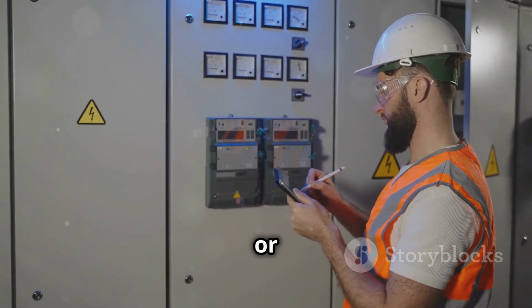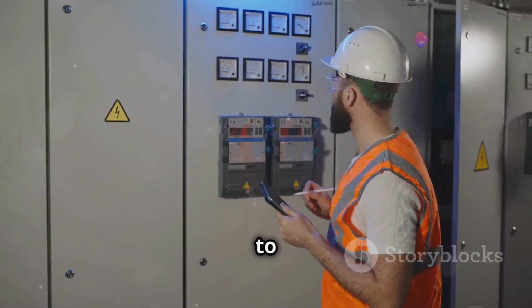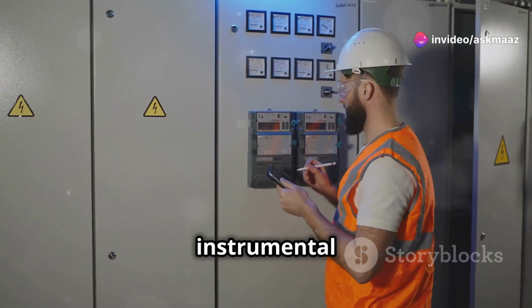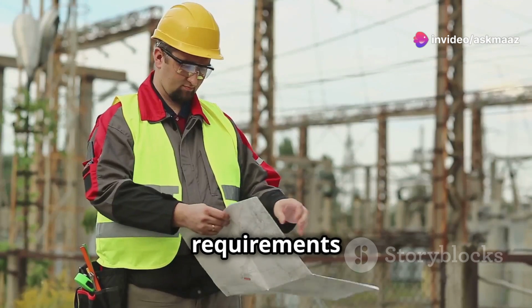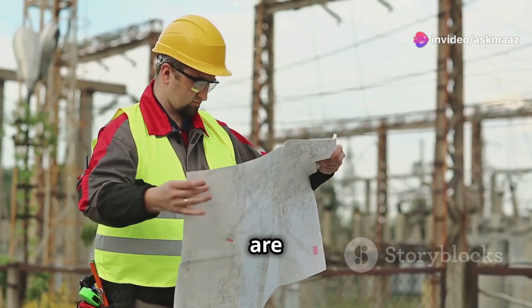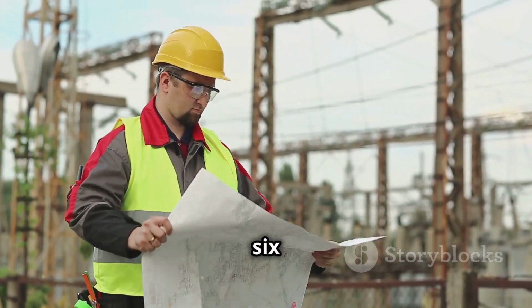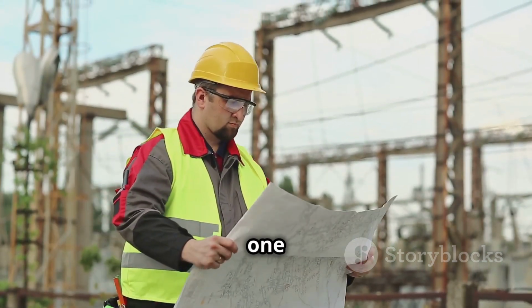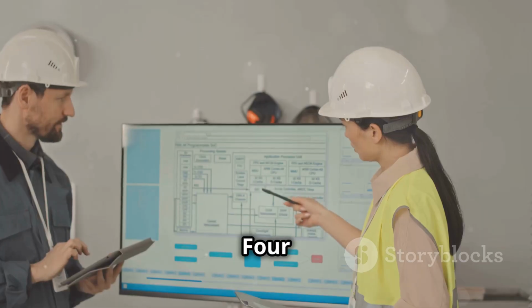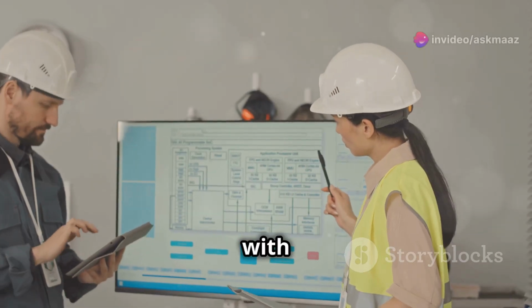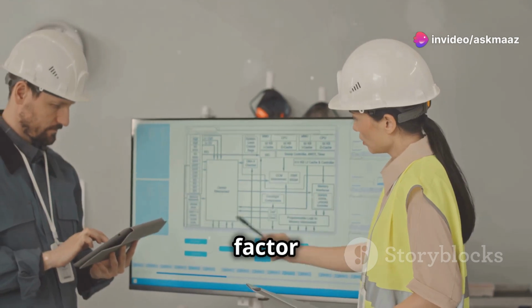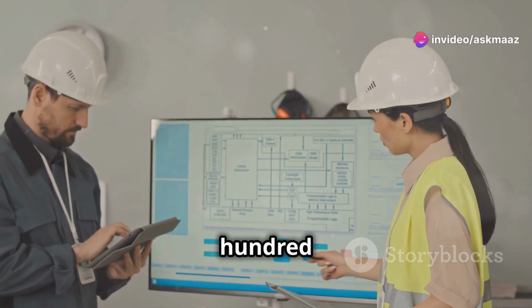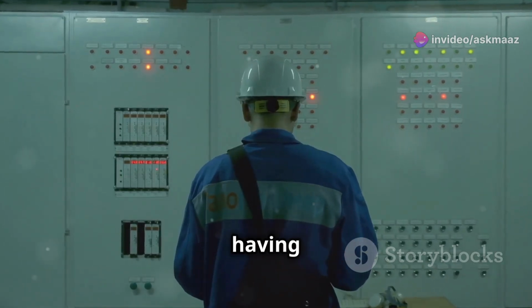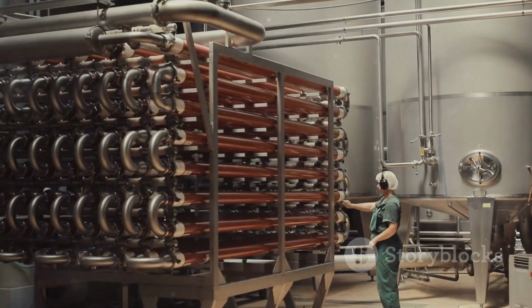Safety integrity level, or SIL, assessments are used to assign risk reduction factors to instrumented safeguards. The requirements for safety instrumented systems are given in IEC 61508 and 61511. Four SIL levels are specified, with SIL 4 having a risk reduction factor of 10,000 to 100,000 and SIL 1 having a factor of 10 to 100.